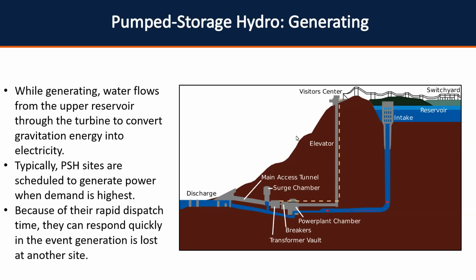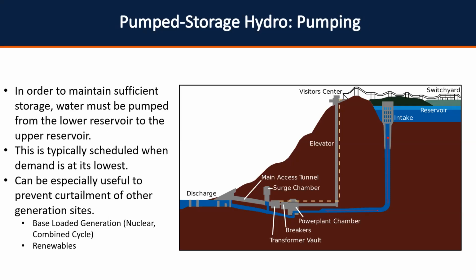For generating, typically in the Southeast, where we don't have a ton of renewables, it's scheduled when demand's at its highest to augment what we have dispatched. One of the big upsides to pump storage is that rapid dispatch time, relative to a combined cycle plant. I work at a combined cycle plant. If we were shut down cold, it would take us several hours to come up. So when we're talking on a scale of minutes, these pump storage hydro sites are pretty quick, and they offer a lot of flexibility. So, pumping, from the lower reservoir to the upper reservoir.